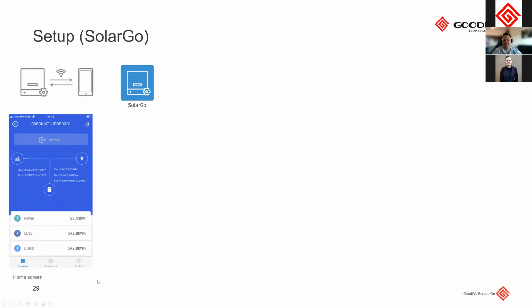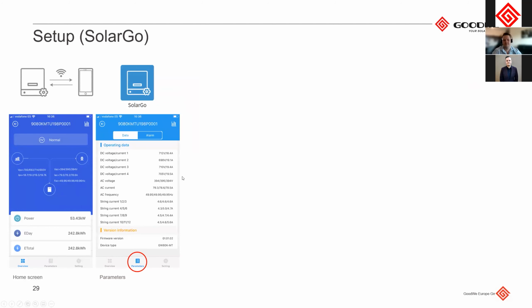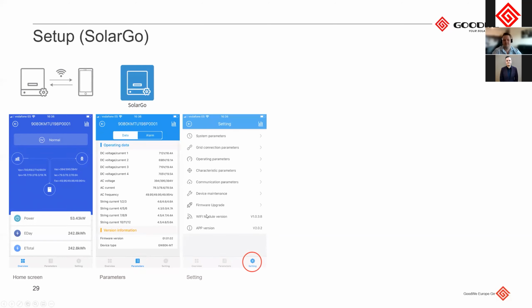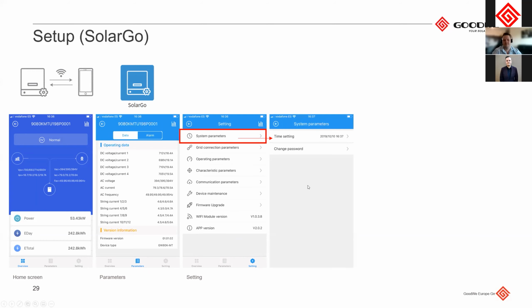So once we open the SolarGo app, you'll see the interface is quite familiar and quite similar to our PV Master application. There you can go to view parameters and you can see all the different information, live running data of the device, as well as the firmware version of your device. And we can go to settings. So in settings, you'll see there are a lot of different looking settings, but for most commercial sites, there's very little that we need to do. The main thing we need to do is just make sure that our system time is correct on the device. So that should by default synchronize with your mobile phone that you're using. So that shouldn't be an issue.